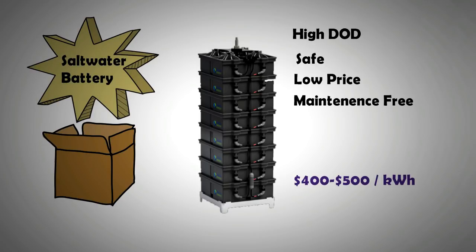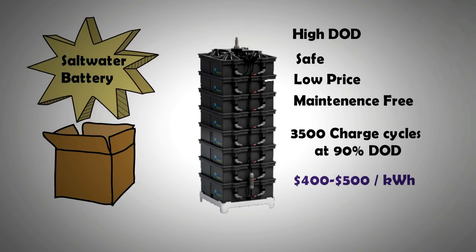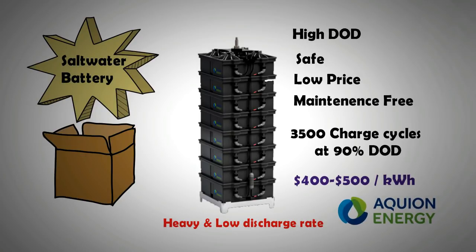The salt water battery has many more charge cycles at higher depth of discharge, making it a more cost-effective option than lead-acid — you can get 3,500 charge cycles at 90% DoD. It does have a couple of drawbacks: it is slightly heavier than lead-acid and can be charged and discharged at slower rates. Currently, there is just one company, Aquion Energy, that is commercially producing it. Prices are expected to drop further with developing competition and economies of scale.